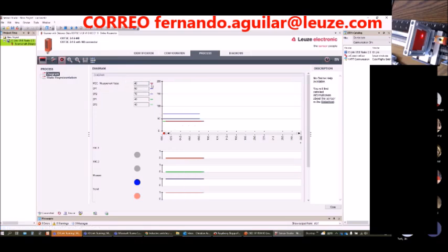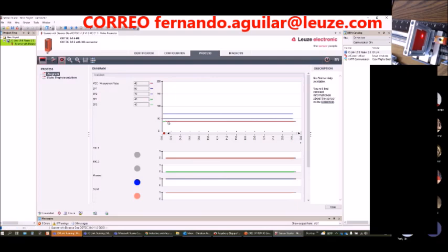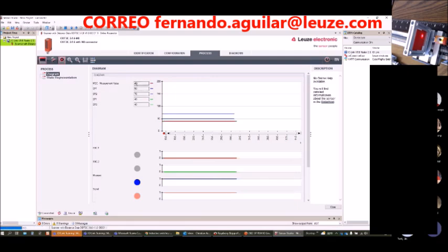And there's several different lines on here. The first line, the red line, that's the actual measurement data. And you can see that the little target has stopped because I have the ODT 3C sending an output to the controller for this drive that'll stop when it reaches a 40 millimeter distance. And that's configured on SP1. So basically it did what it was supposed to. It's set to 40 millimeters. The output went low and it stopped the device.